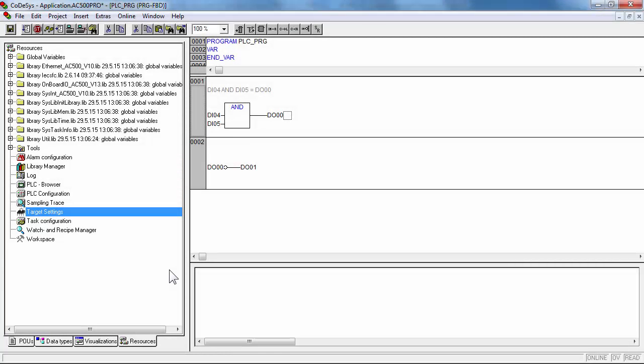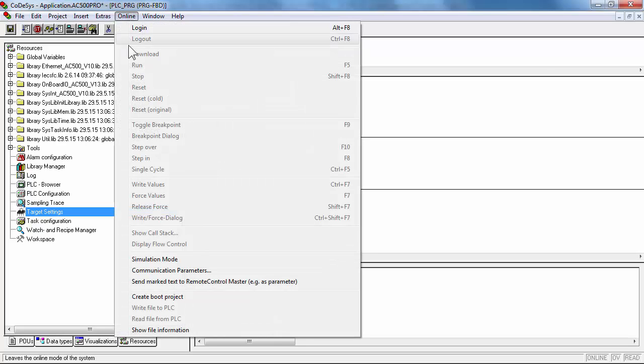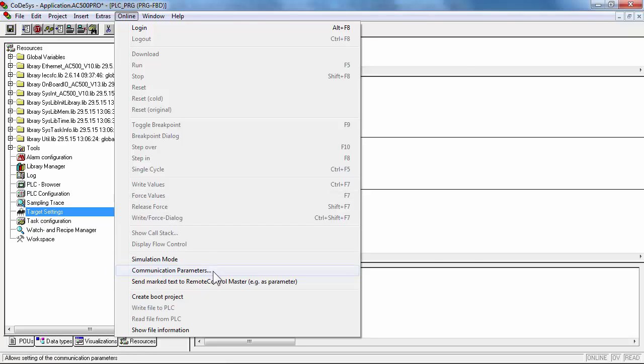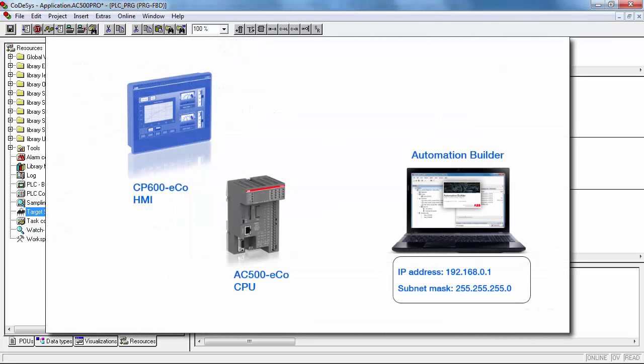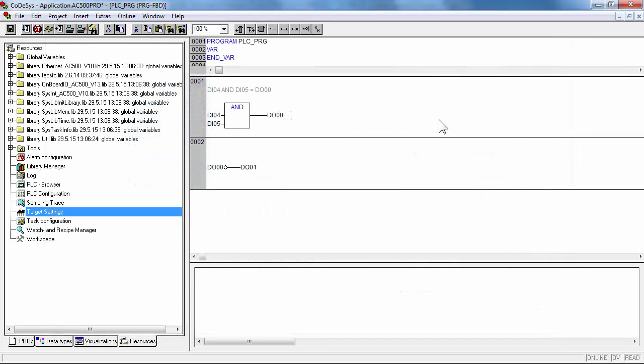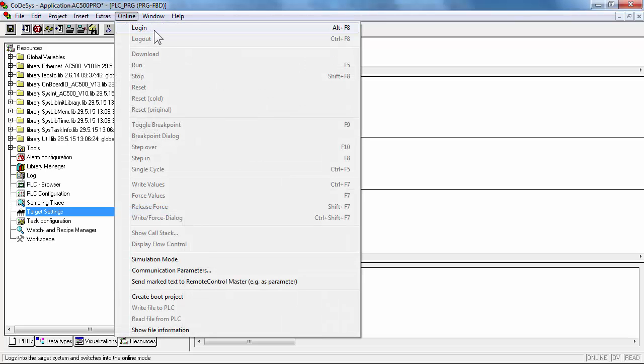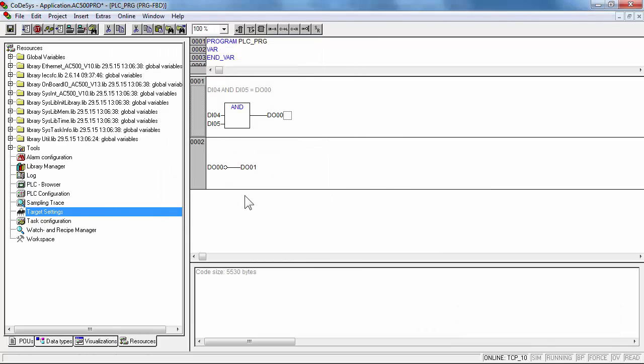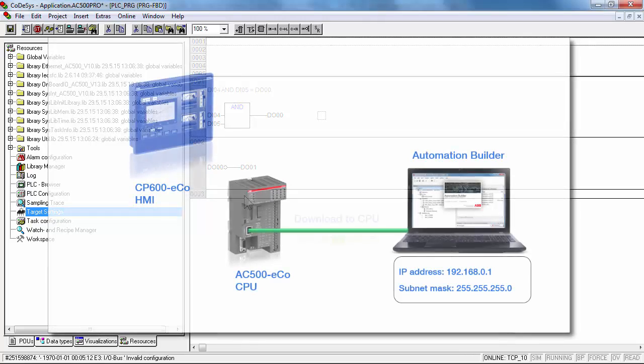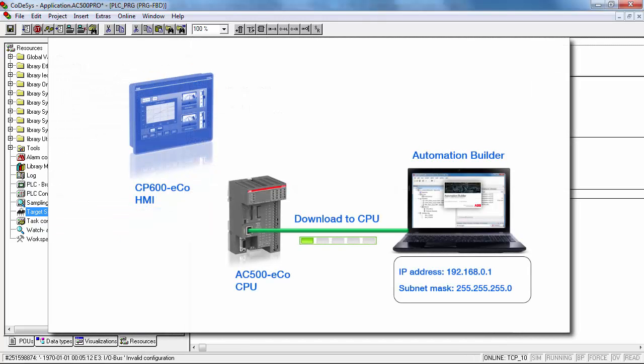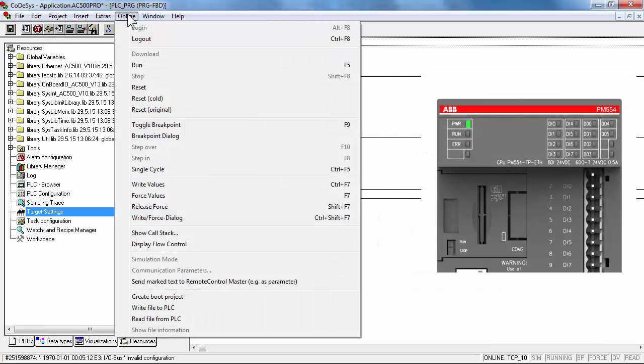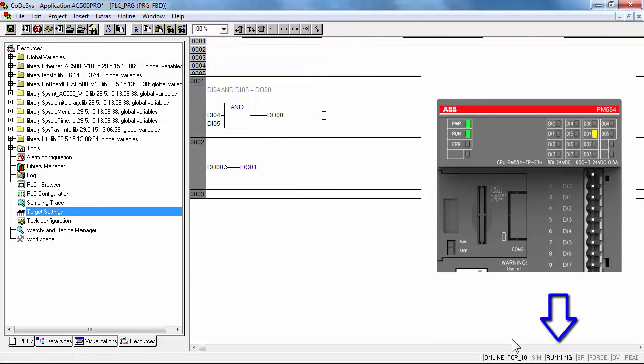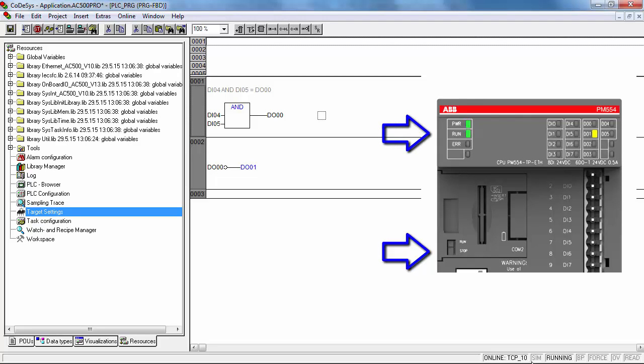Start by AC500 ECO CPU and from IEC 61131 application. Verify that the communication parameters are according to the IP addressing of your CPU. Connect the Ethernet connection between computer and CPU and download your program after logged in action. The CPU should be in run mode operation to execute the PLC cycle. So verify on CPU that the run-stop switch is in run position and that run LED in the front face is displayed in green.